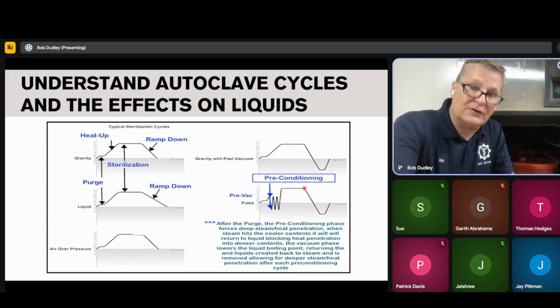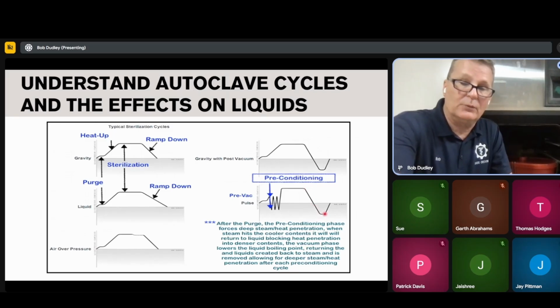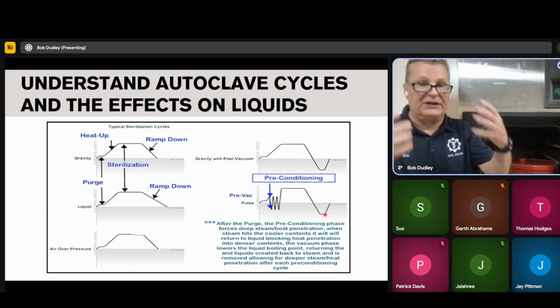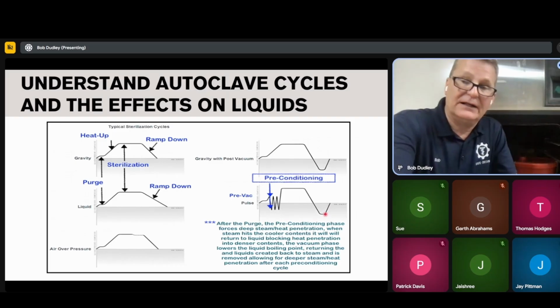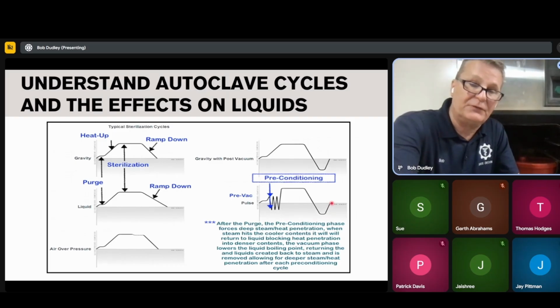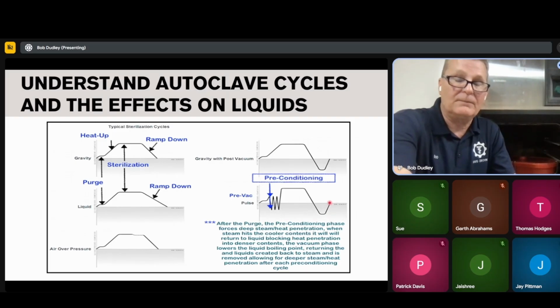And then, of course, when the sterilization's done, it's going to kick it down. Generally, as a rule, it will run into a dry phase. Some people run 1 minute, 5 minute, 10 minute. What this is doing is pulling out any mist so that when you open the door at this point, you don't get a face full of steam or any other problems, and it goes back to atmospheric, and this is where you can open up the door.